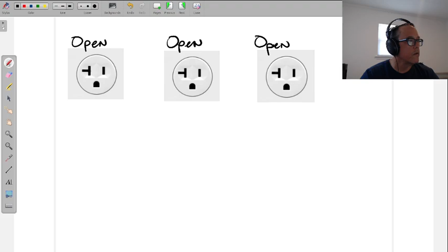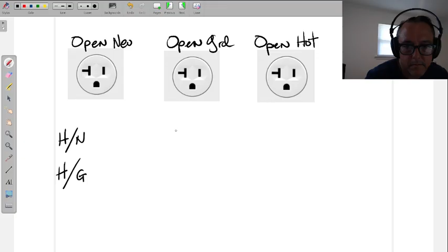And then what is missing? So open neutral, open ground, or open hot. And using your meter, it's very easy to determine which one is missing. One of the things that you want to do with an outlet is double tap, check twice, check between hot and neutral, all right, in all cases, and then check between hot and ground. So that's how we're going to set this up. We're going to do a double check, hot neutral, hot ground.